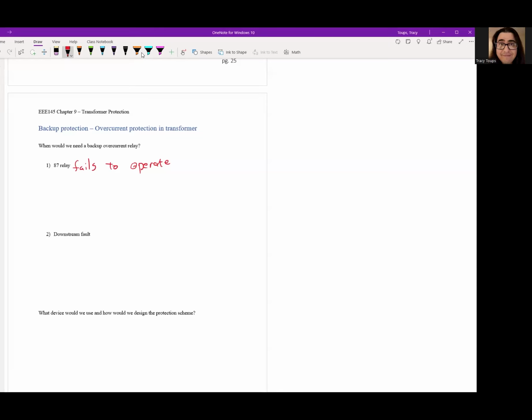So it never hurts. Again, a classic 50-51 overcurrent element is always there to protect, is very reliable, and they're pretty much everywhere. So the 50-51 overcurrent element is the backup protection. Again, in an SEL relay, when you buy a transformer differential, like an SEL 387, it's going to have 87. It's going to have all your restraints. It will have a built-in 50-51 overcurrent for you as well. So they're all prepackaged in one box for microprocessor relays.